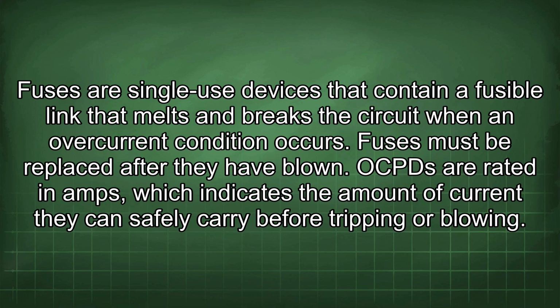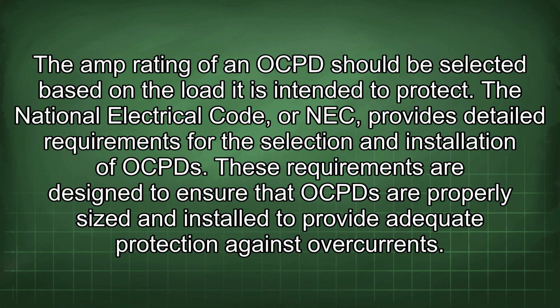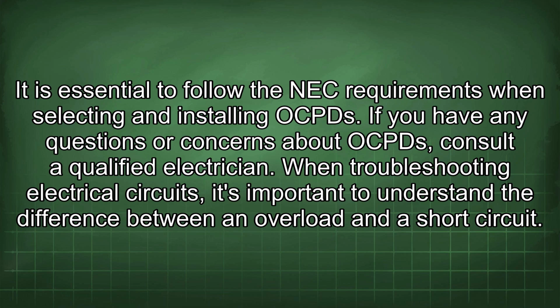OCPDs are rated in amps, which indicates the amount of current they can safely carry before tripping or blowing. The amp rating of an OCPD should be selected based on the load it is intended to protect. The National Electrical Code, or NEC, provides detailed requirements for the selection and installation of OCPDs. These requirements are designed to ensure that OCPDs are properly sized and installed to provide adequate protection against overcurrents. It is essential to follow the NEC requirements when selecting and installing OCPDs. If you have any questions or concerns about OCPDs, consult a qualified electrician.